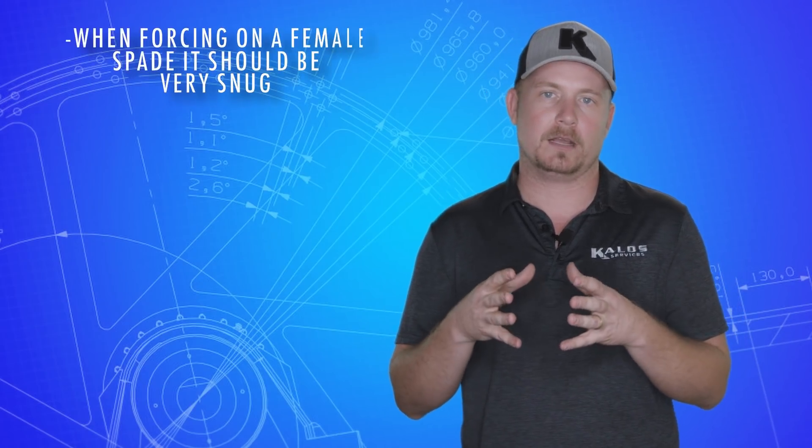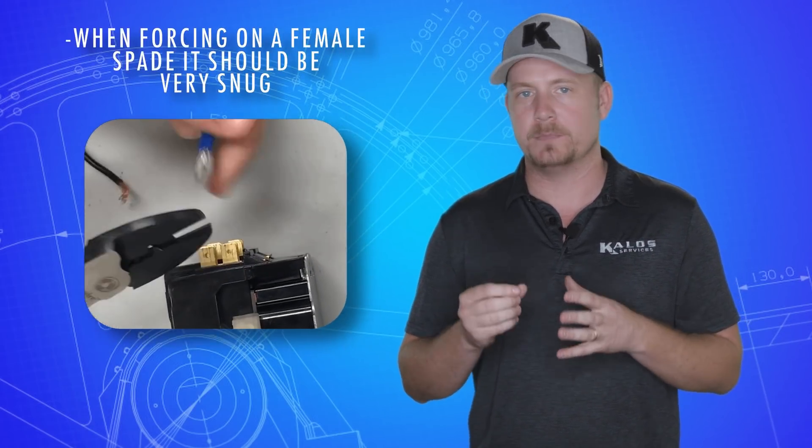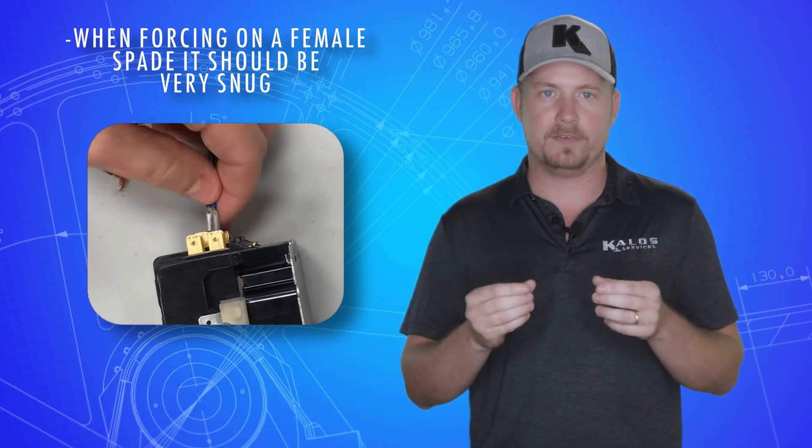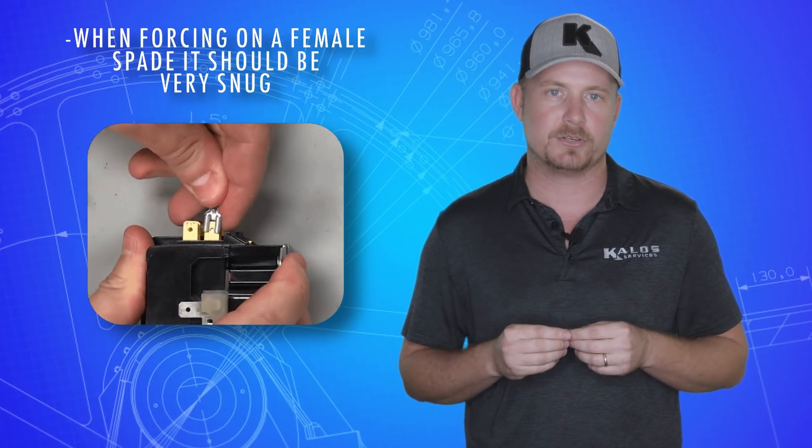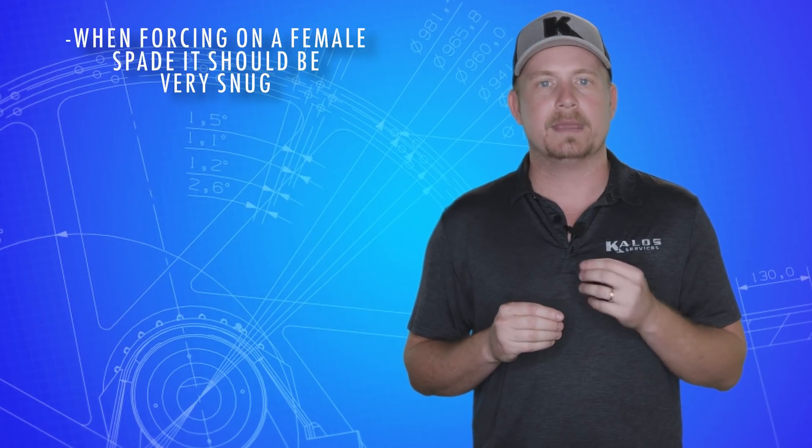When forcing on a female spade on a capacitor, for example, it should be very snug. If it's loose at all, pull it off and pinch down the spade sides a bit to ensure there's a snug fit. When making a crimp connection, only do so on a stranded wire and use an appropriately sized connector.